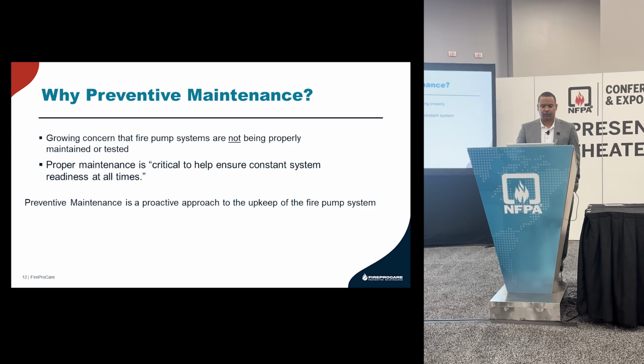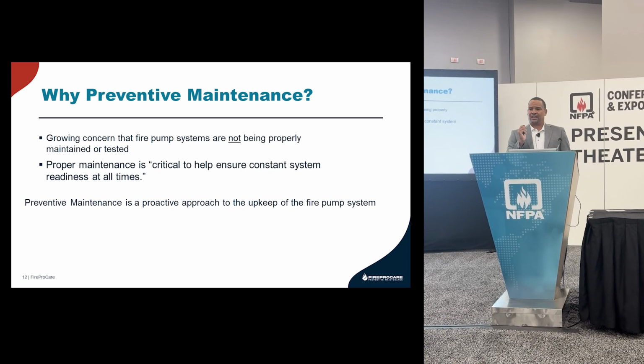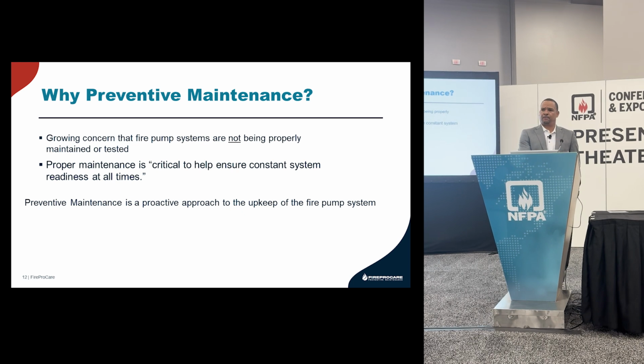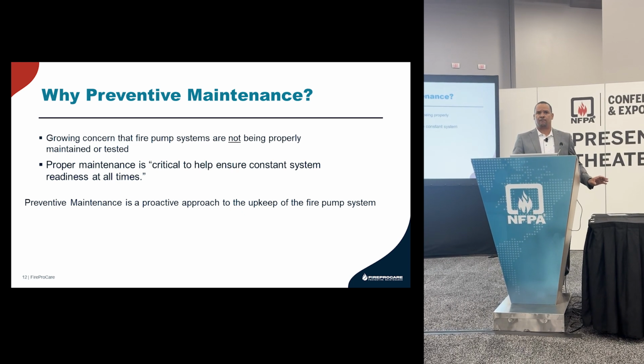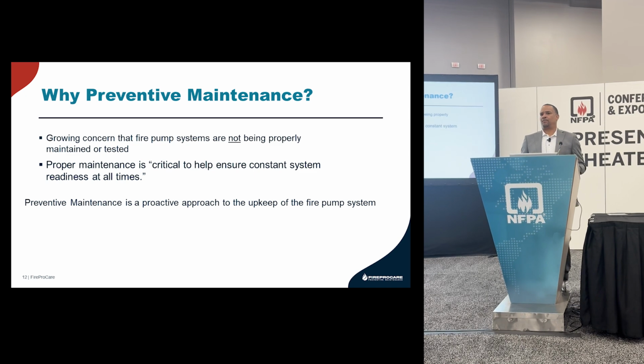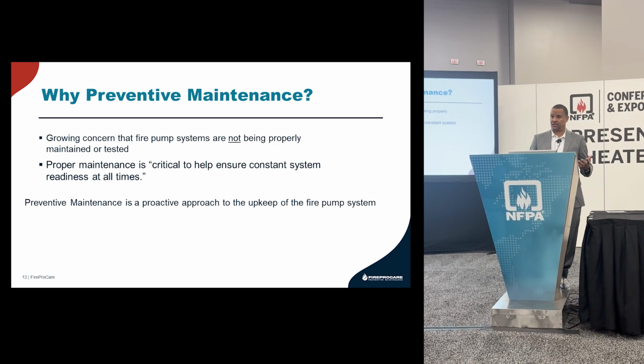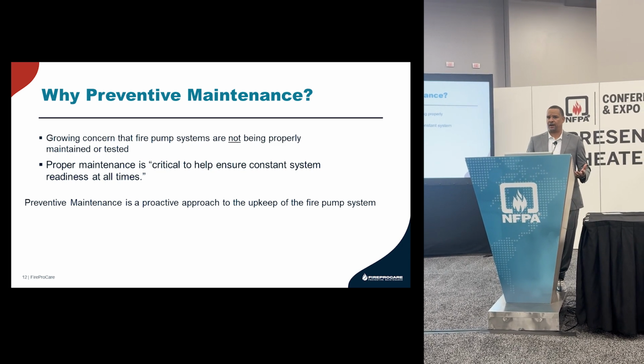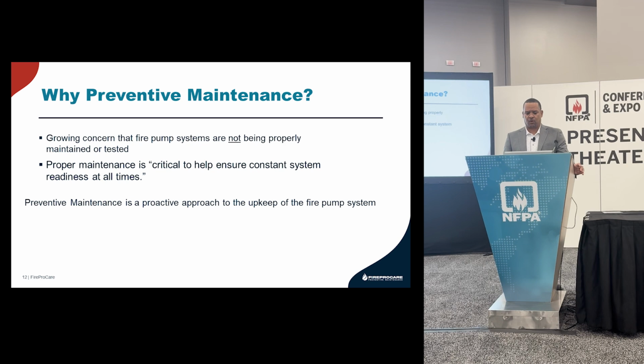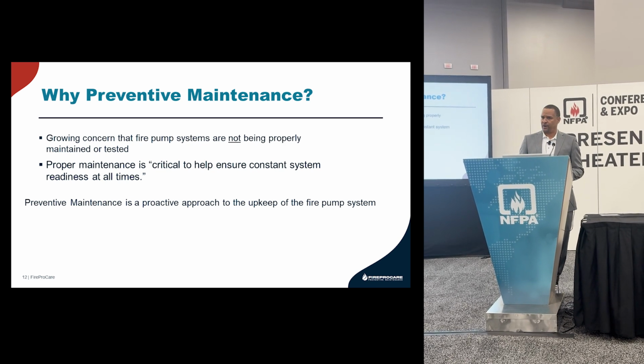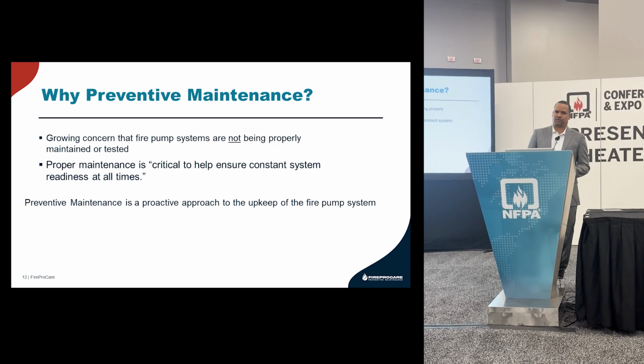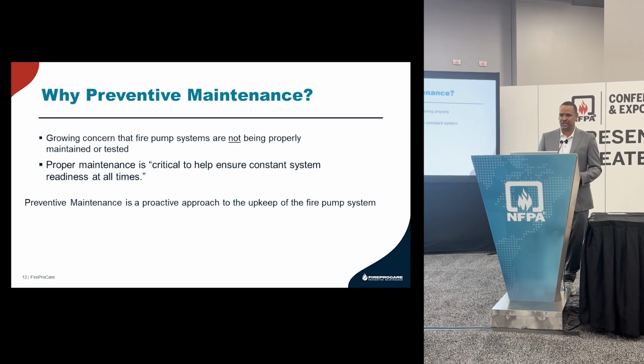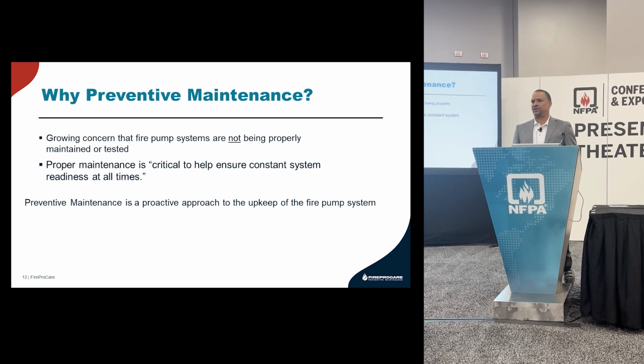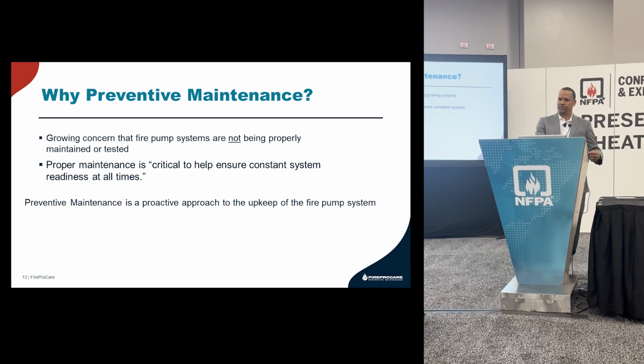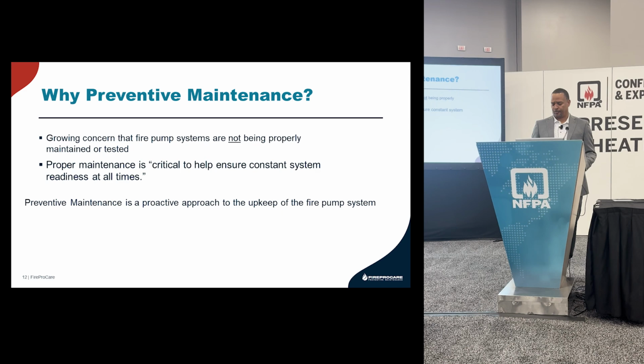You have to understand when that system goes in place, the fire pump is something that's in the basement, it's dark, it's away. As long as there's no alarm, no one's going to pay attention to it. That's a problem. You hope it never runs. If it does run and there's a catastrophic reason for that, the building is on fire. However, without that preventive maintenance program, it may not be ready to operate when necessary. Proper maintenance is critical to help ensure constant system readiness at all times. You need this PM program. You've got to have something in place for the controller as well as the pump and the driver. You've got to have that.